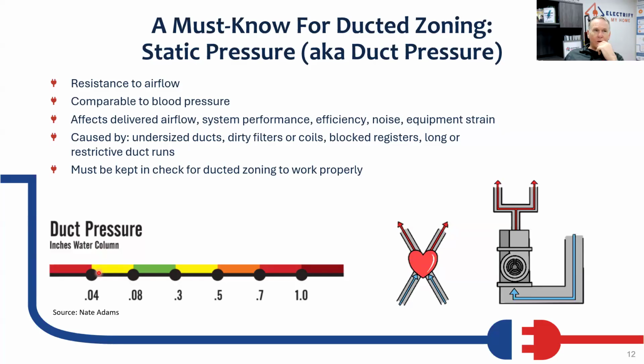Now there is some conversation about what does it mean if I have a system that has ultra low static pressure? That can be a problem too, because we can't build up the velocity and everything else we need in that system. It affects delivered airflow, system performance, efficiency, noise, equipment strain. Undersized ducts can cause this problem. Dirty filters, blocked registers, long or restrictive duct runs, or multiple zone controlling systems. And for the ducted zoning to work properly, we have to keep these numbers in check.